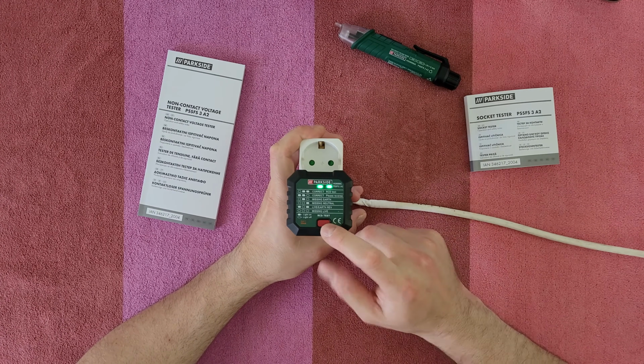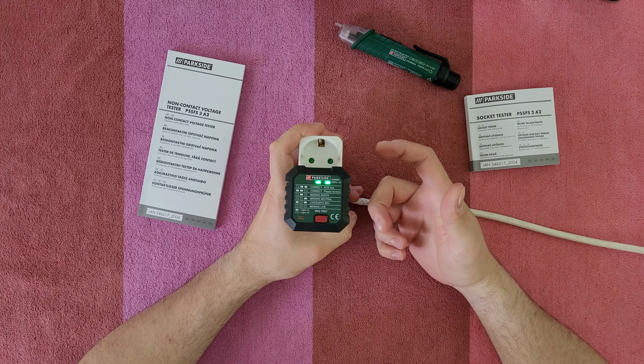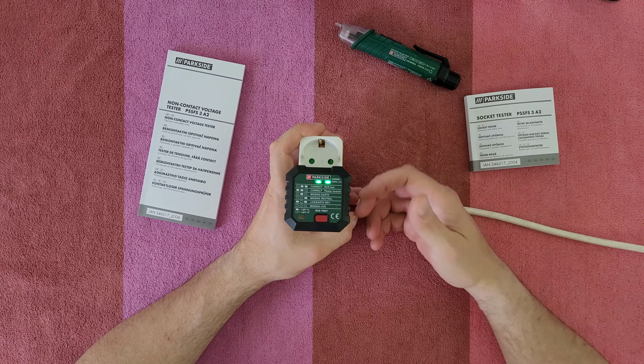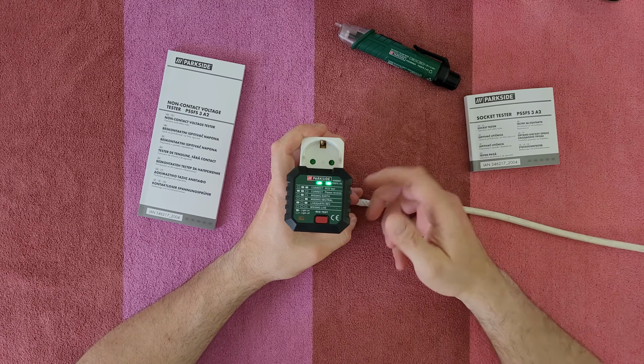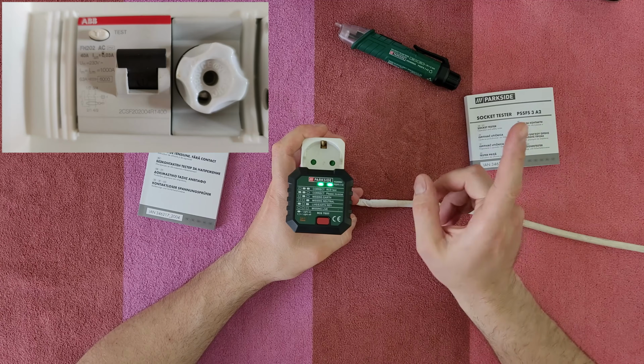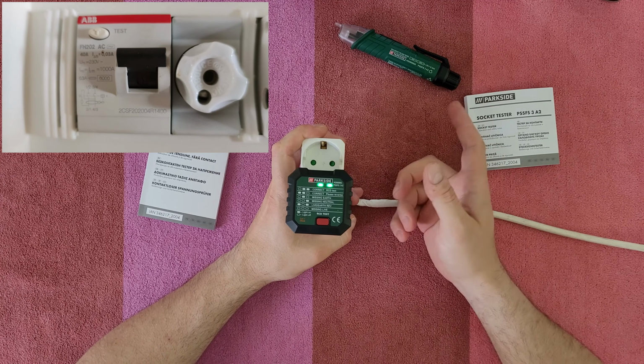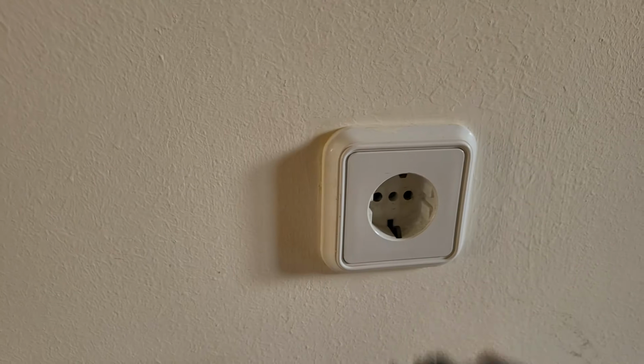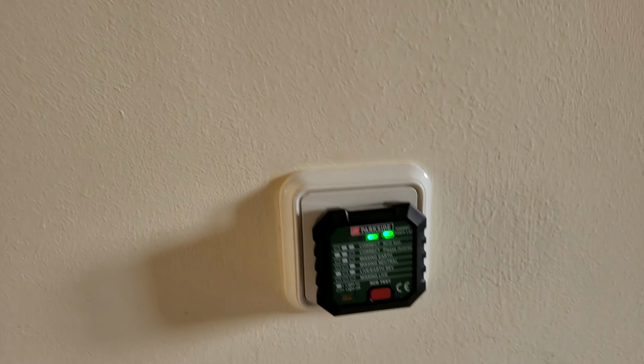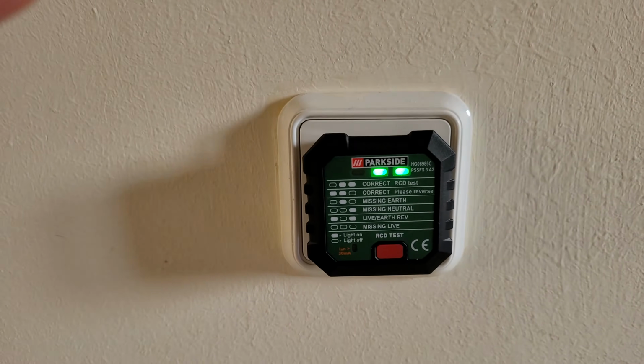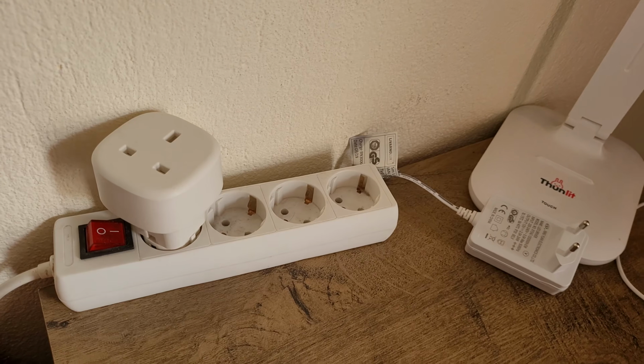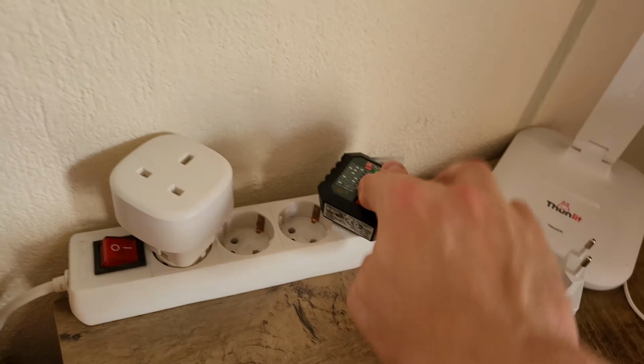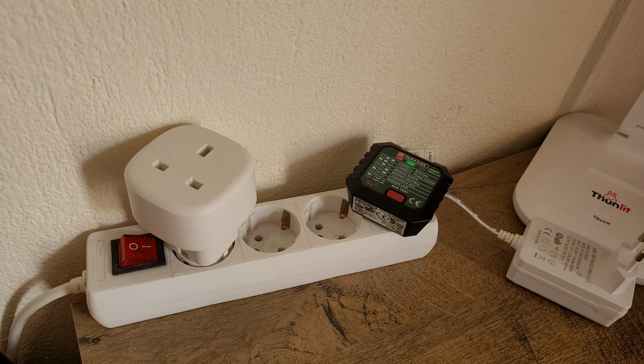When I pushed this button, the RCD was turned off - that means we have tested it and it's working. Of course, all RCDs have a button on the unit and you can press it and check if it's working. You can plug it into some other socket and again we can see everything is working perfectly.